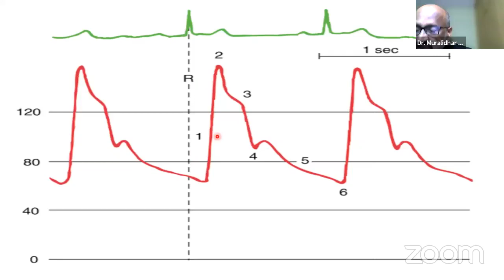When we talk about pressure monitoring, we need to understand that there are 3 physical principles. These are the frequency response, that is the ratio of measured versus input amplitude. At a given frequency, it should ideally be 1. That is, whatever is the pressure in the system should be measured and recorded the same. That is, the relationship between the pressure and the measured pressure should be 1.